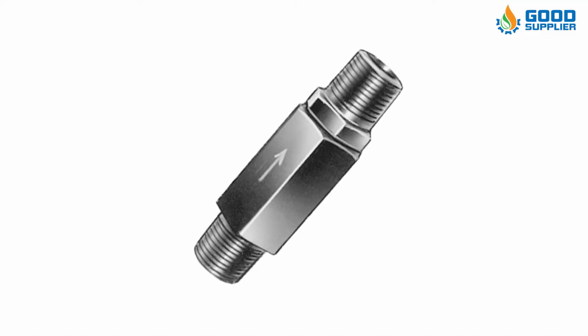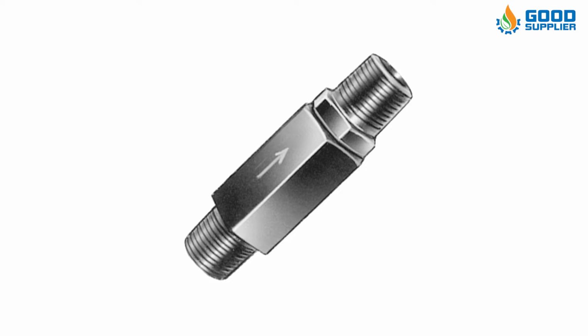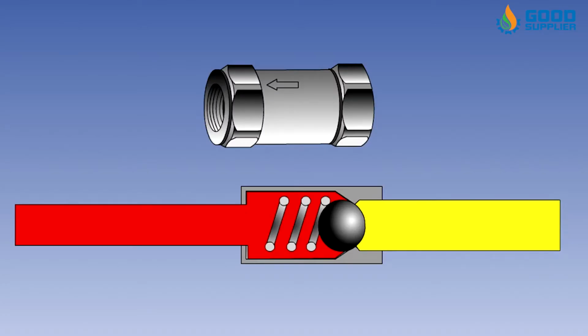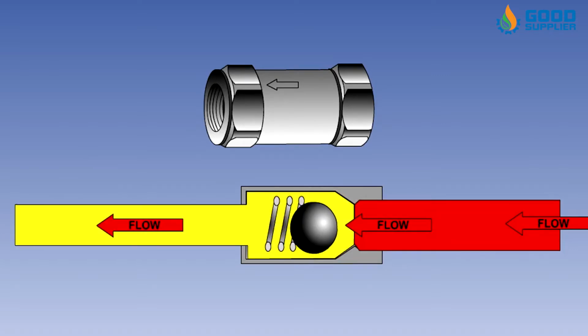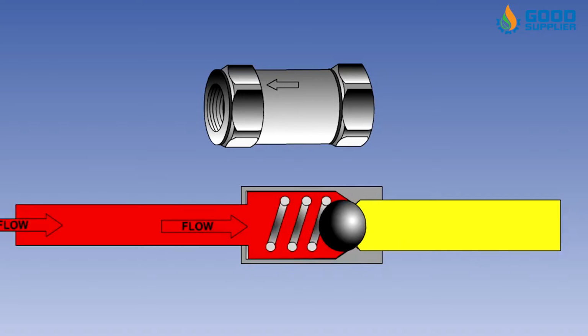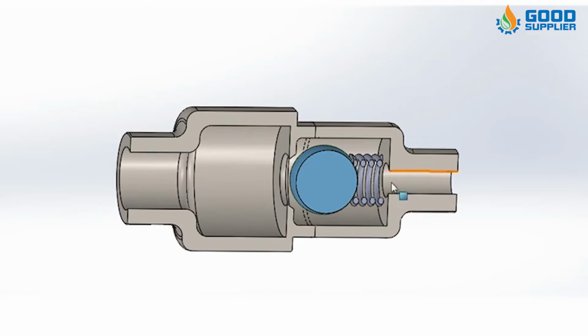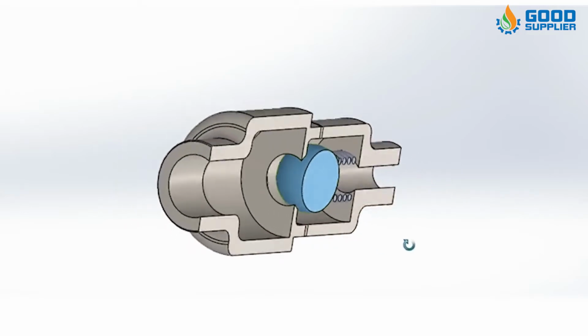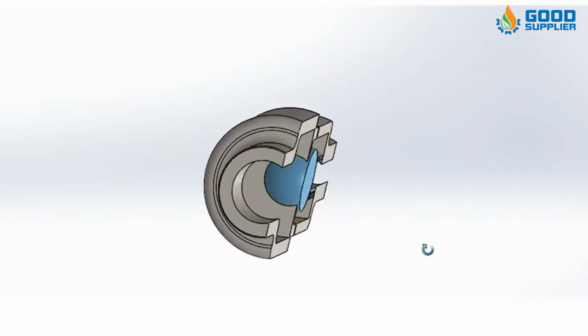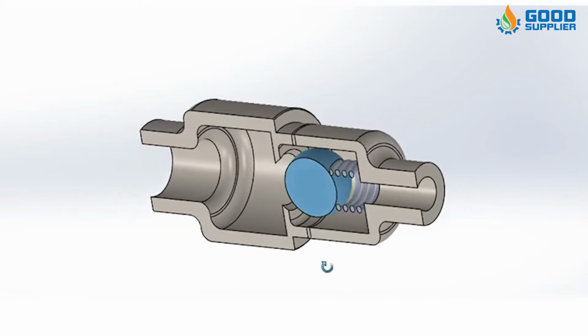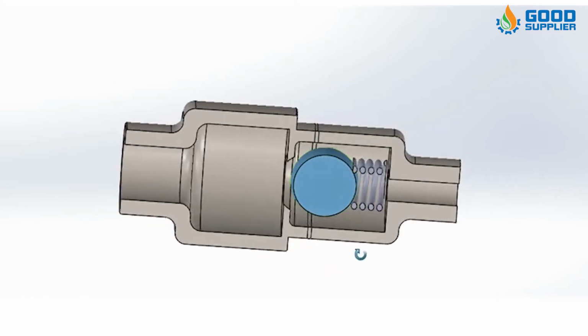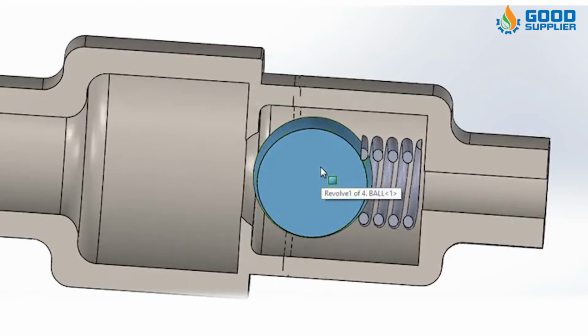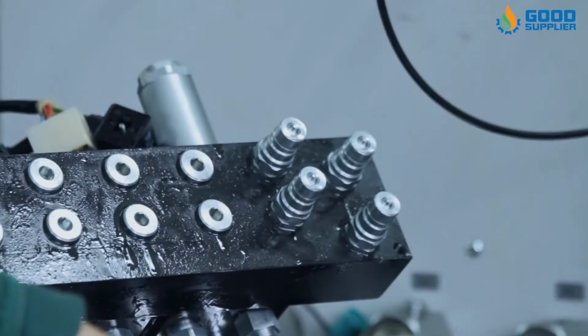A ball check valve functions using a ball that moves up and down inside the valve. The seat is machined to fit the ball, and the chamber is conically shaped to guide the ball into the center to seal and stop a reverse flow. Hydraulic check valves are used in many hydraulic systems. They are used to protect the heat exchanger and avoid overpressure when the heat exchanger is blocked. At the same time, the heat exchanger can also be bypassed.